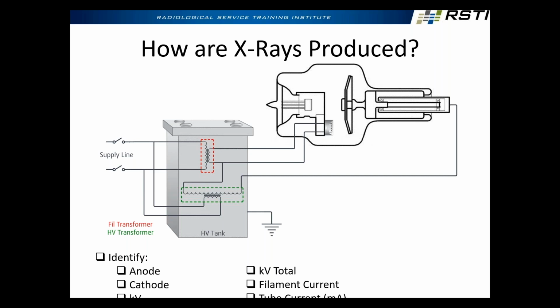Now, what we're looking at here is the absolute most basic setup we could possibly produce as far as the generator is concerned, not as far as the tube is concerned. The stationary anode would be even simpler. But what's going to happen is our incoming power here, single phase, is going to get stepped down to somewhere between 4 to 5.5 amps of current, around 6 to 12 volts for our selected filament. And the high voltage that's going to be supplied to the tube is going to be somewhere between 40,000 and 150,000 volts, right?